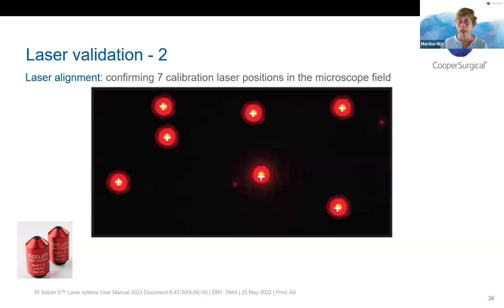So the laser alignment, and I'm using the Saturn example, this is an active dynamic laser. It will move to different points that you indicate. So how does it work? Well, it's 7 calibration points that you will confirm. It will move to these 7 different points, and that is so quick. As you can see, it's not even 1 minute, and you have done your laser calibration before you continue your work, and you're sure then that you are hitting where you want to hit with your laser. Another important aspect of the validation and checking the quality of the working of the laser is to look at the hole size.